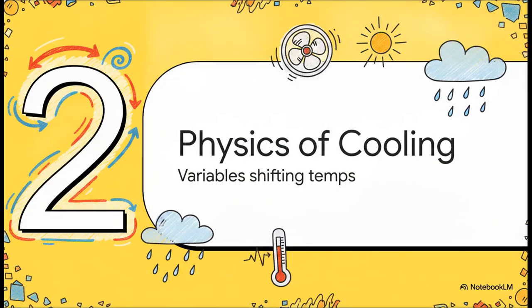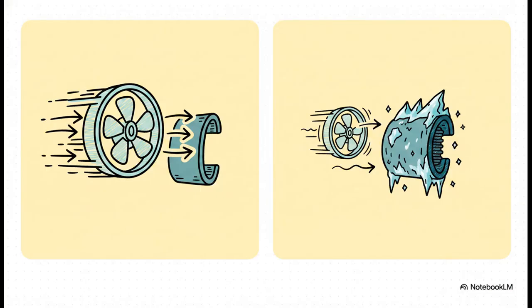Moving on to part two, the physics of cooling and the variables that are constantly shifting these temperatures. So, your first major variable is airflow velocity, basically your fan speed. If you crank up that fan speed, you are moving a whole lot more warm room air over the coil every single minute. That high thermal load actually keeps the coil slightly warmer, typically closer to 8 to 10 degrees Celsius.